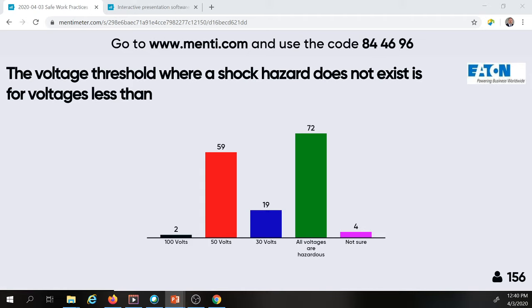The additional hazards: you're going to identify your hazards, you're going to look for your normal approach. I'm trying to find the section in the 70E. If you have that section offhand for your shock hazard, please ring it out. Check and see. Yep, 70E is 50 volts, and some of the UL standards. There we go. Qualified persons insulated.